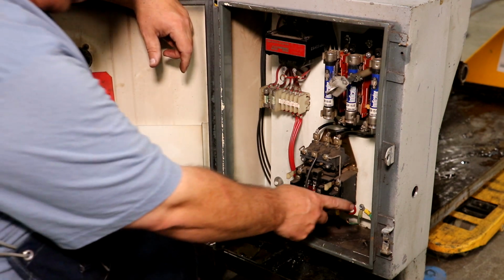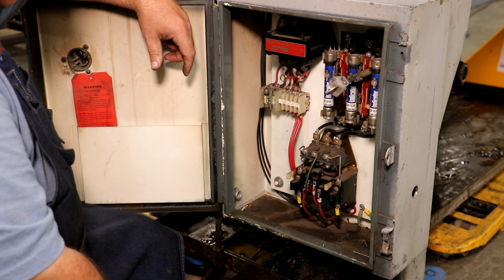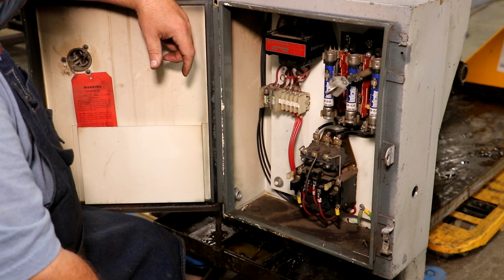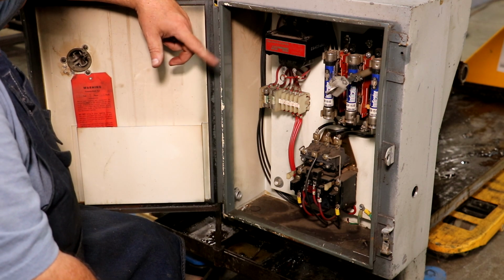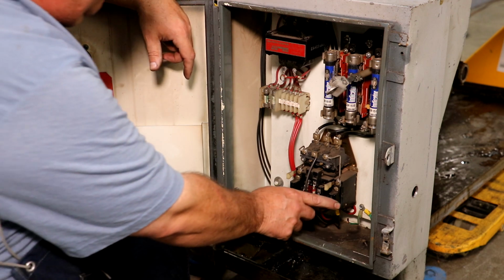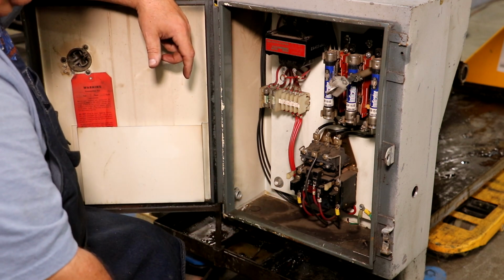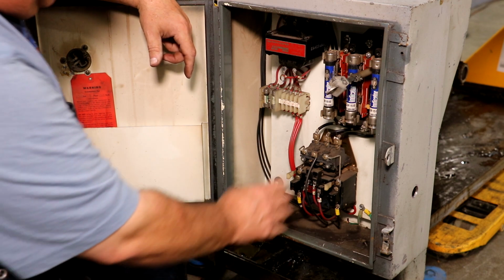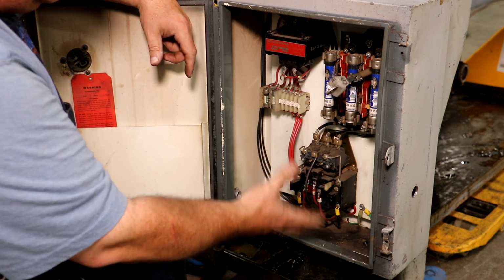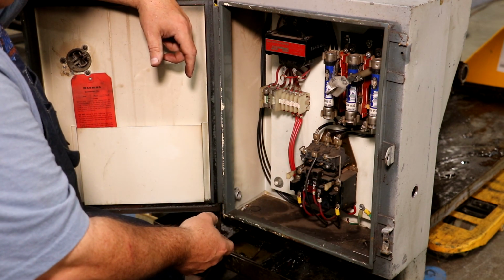But these are set to protect your motor. Again, at 480 volts, the motor only draws 2.5 amps. So this is designed so if it starts drawing more than 2.5 amps, it opens up the circuit and basically collapses the circuit and shuts the machine off. It's just to protect your motor.